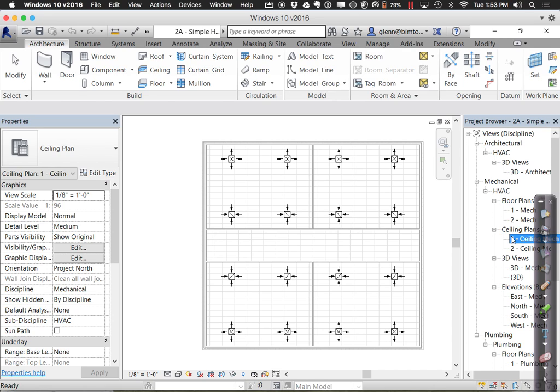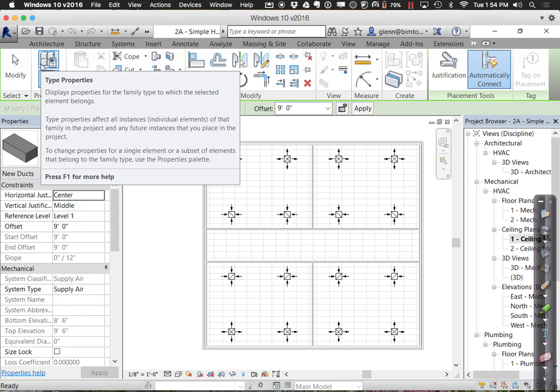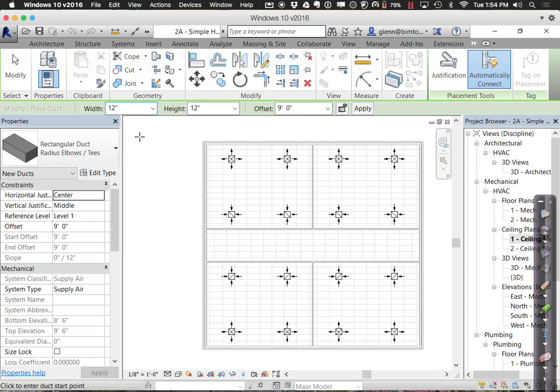We have some basic space here. We're going to put an air handler right here above the hallway. Let's try connecting some ductwork first. For ductwork, you go to the Systems tab, choose Duct, and start placing. Notice in the options bar: watch out for the default size as well as the offset. That offset is measured relative to the current base level, so if our current base level is one, it will be nine feet above. You could also say it's a foot below level two, but I tend to do it from the bottom up.